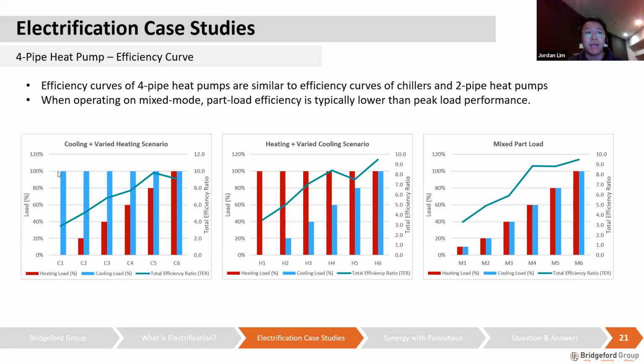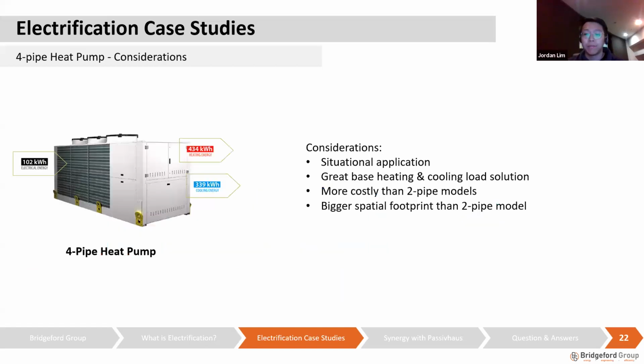As you can see here, if we maintain a flat cooling load of 100%, but with different scenarios that describe the different part load values and also the peak load value for the heating load, you can see that the efficiency of the heat pump is actually quite high when it's running close to peak conditions. But as either the heating load or cooling load goes down, the efficiency also drops. And likewise, if both your heating and cooling loads are at the very highest, the efficiency is at its very best, and as it goes down, it also drops. So that's why a system like this is best applied as a base load application, and the rest of the heating load and cooling load is made up by other technology instead.